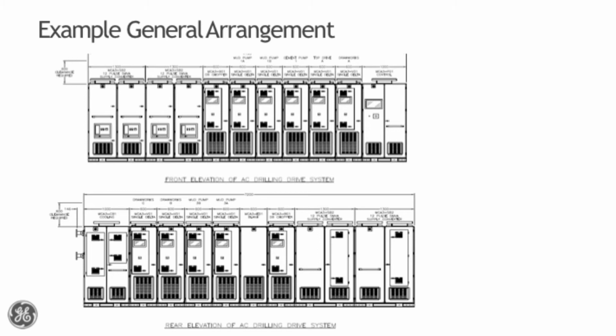It's a common DC link, and it is the highest level of fault current you will get on these vessels, because it feeds in from all the generation switchboards, and it has one common DC link which feeds multiple different load feeds. So we have all of these regenerating energy sources in the motors coming through onto this DC link. We have an enormous amount of capacitors, and we have feed in from every single generation switchboard into this board.